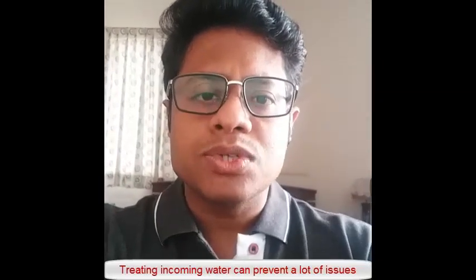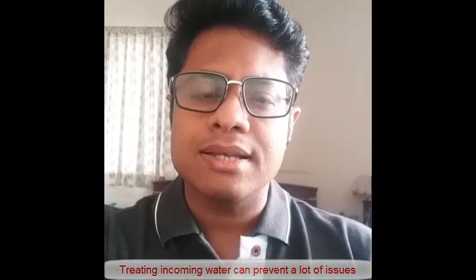When you see two cylinders, the standard ones people put are a sand filter and a carbon filter, together with a softener sometimes. The first cylinder you generally see is a sand filter, which is meant to reduce the turbidity of the incoming water. If the water is not clear, the sand filter will reduce particles and make it a little clearer. They use different grades and sizes of sand so the particles are filtered. However, for higher turbidity, there are different materials available for filtration.